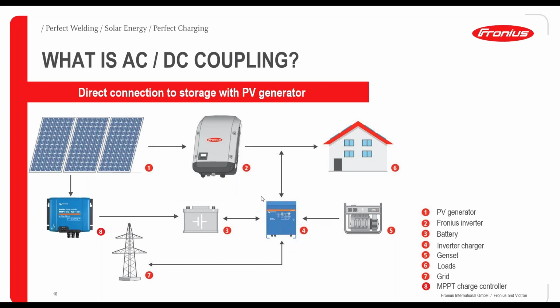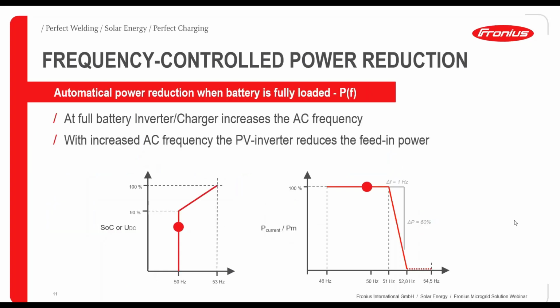We can have perfect communication, and you may ask how this communication is done between Fronius and Victron. This brings us to this phenomenon, the frequency-watt curve, meaning we communicate with all Victron devices via the inverter charger through frequency controlling.